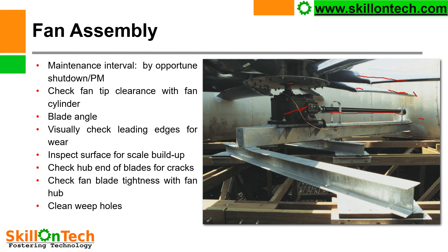Check the hub end of the blade for cracks. The junction of the hub and fan blade is a very weak portion of the fan blade assembly and may fail from this portion. If any crack is observed, the complete blade shall be replaced. Check fan blade tightness with the fan hub — the fan blade should be properly tightened with the fan hub, and fasteners shall be checked. Weep holes of the fan blade shall also be cleared.